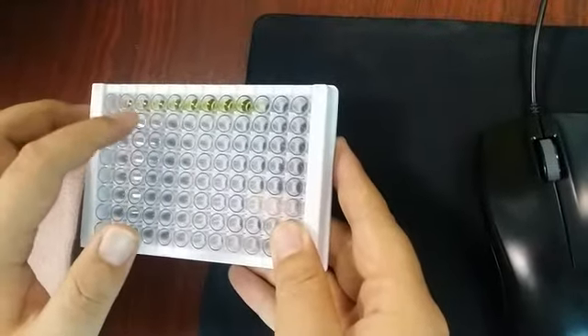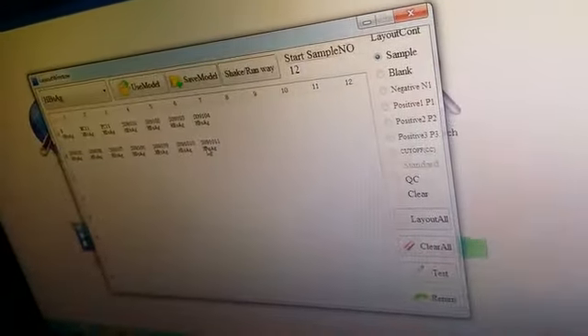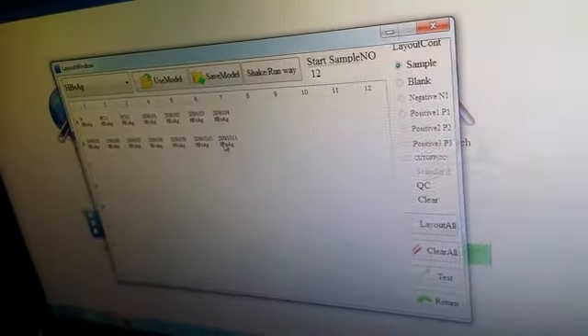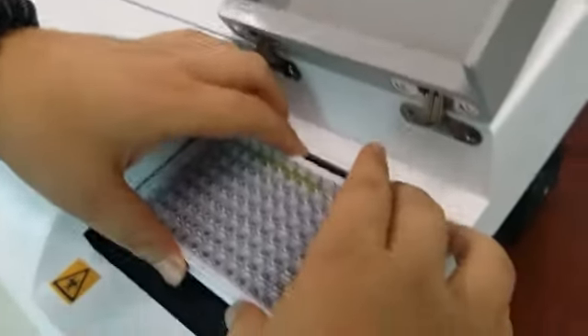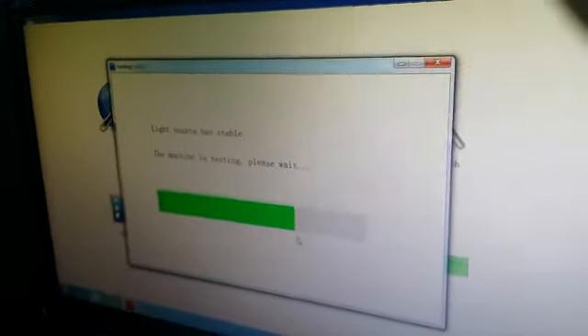It's also according to you, but you should mention one thing. If we put the region and the sample here, we should also put the blank and the positive region and the sample the same as this. Please be noted, they should be the same as this. Then we put the region and the sample to here, carefully, and then cover it. After we do that, we just press the test key and wait 15 or 20 seconds, and we will get the results.